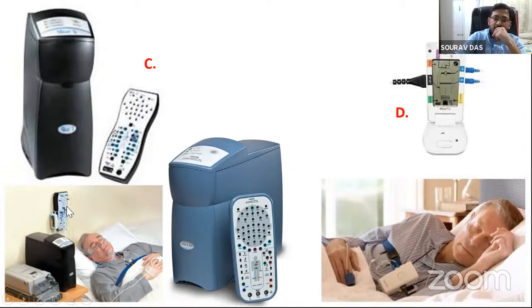So when we fill all those spaces, it will look more like a sci-fi movie, with a lot of wires and leads being attached to the person's head. There are leads for the masticatory muscles of the patient. There are leads for limb movements attached to either the legs or the arms or both sometimes. And we can also have, as an option, the facility to record the entire thing through infrared videography, which will help us find out a lot about movements. So this is a level 1 device, and this is called a level 1 study, where we monitor a lot of different parameters which I just mentioned.